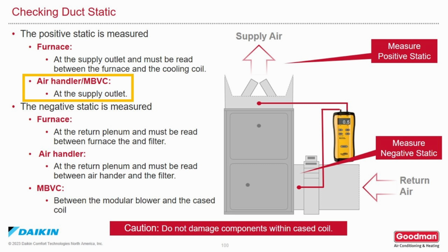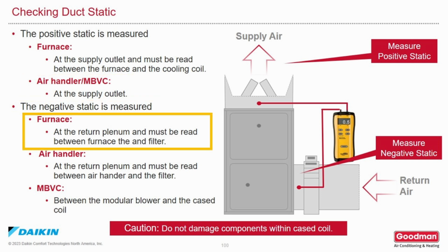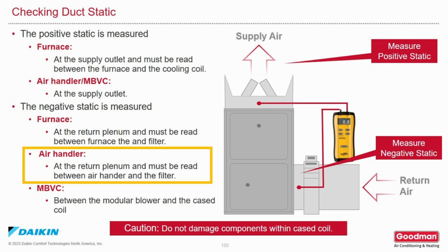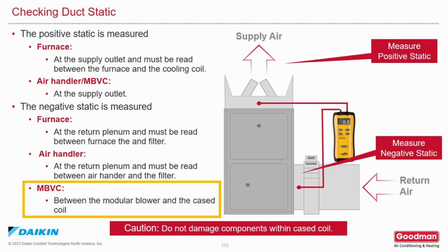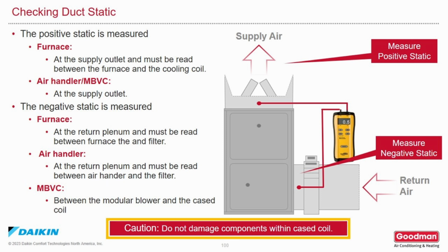On an air handler and MBVC should be measured at the supply outlet. The negative pressure on a furnace should be measured at the return air plenum and must be read between the furnace and the filter. On an air handler, at the return air plenum must be read between the air handler and the filter. On the MBVC, negative pressure should be measured between the modular blower and the cased coil. Please be very careful when you're drilling holes in the cased coil not to damage the coil.